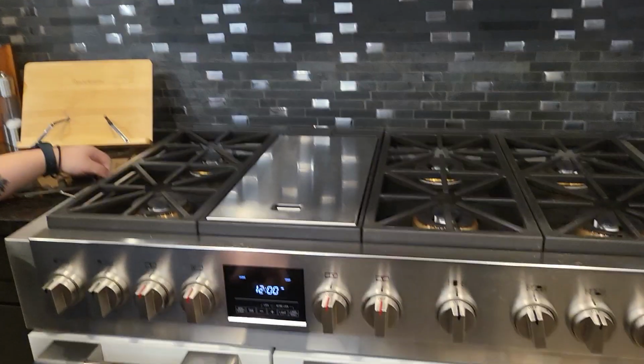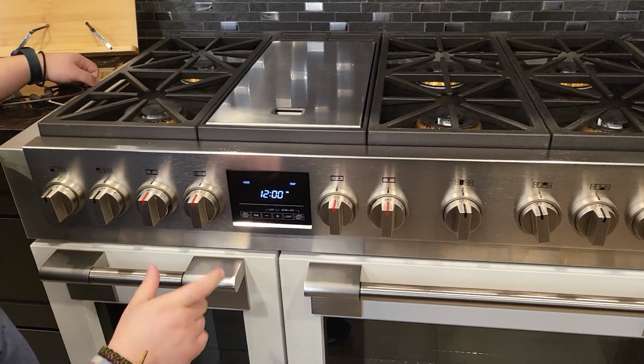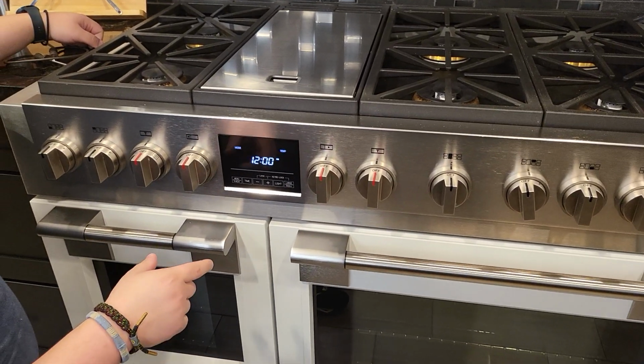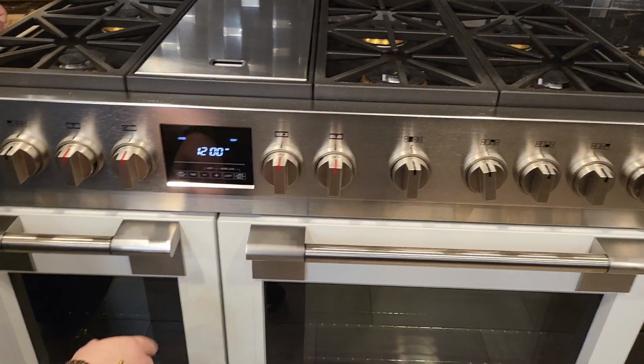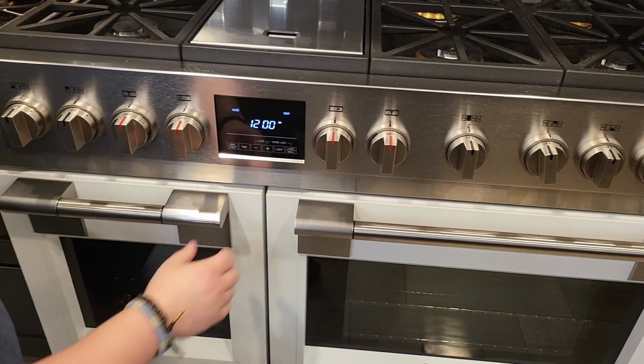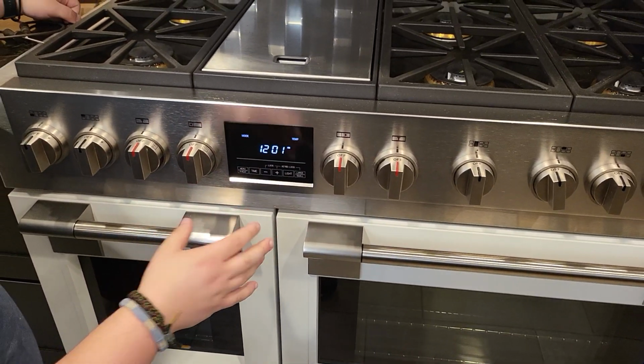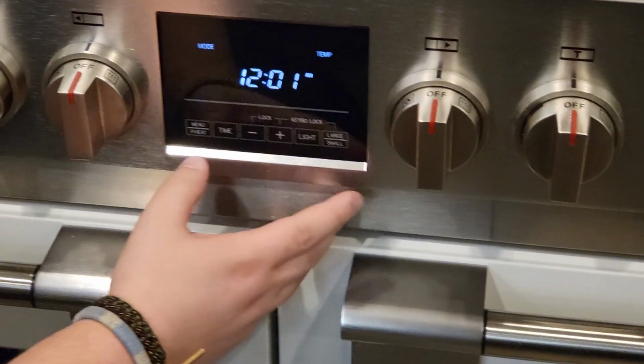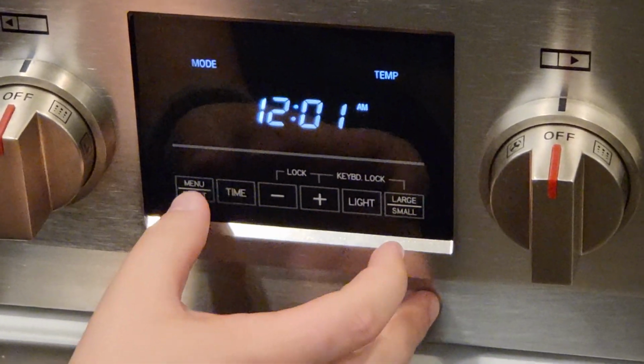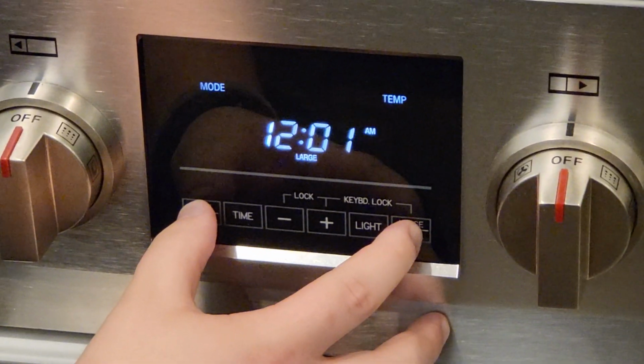All right, so we're doing a 48 range after a power reset or for the F11 error, which is the programming of a new board. We've done a power reset and brought the power back. You can only do this test within the first 5 minutes of repowering it on. You're going to start by holding the far left and far right buttons at the same time for about 5 seconds.